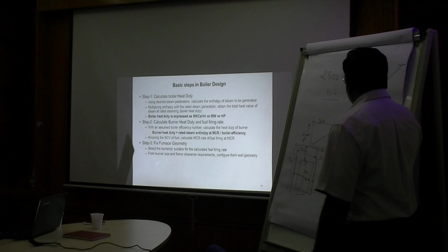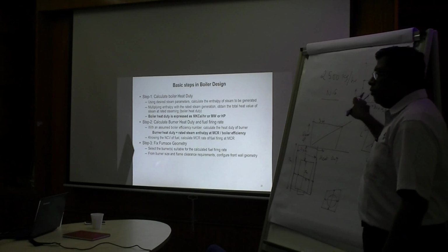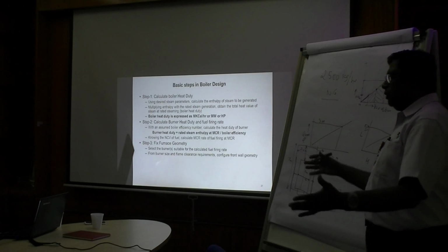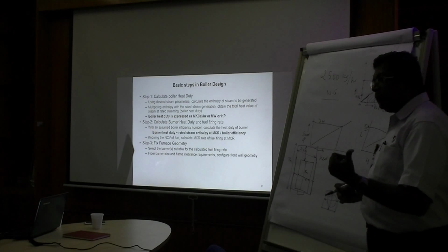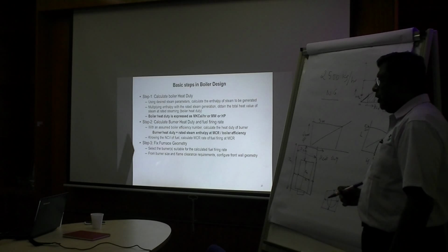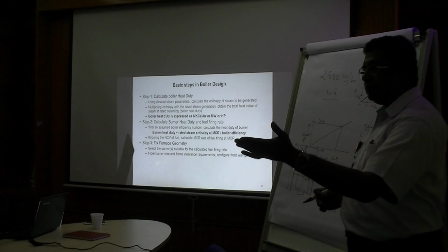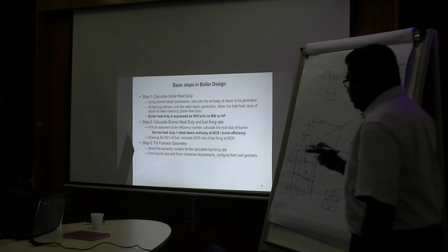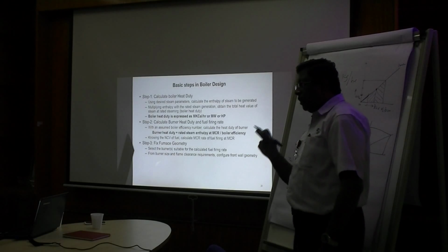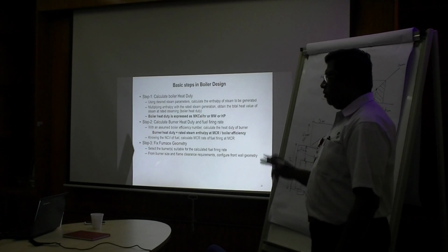So when you go for selecting or doing the engineering review, for example, you should ask the question: why are there only 2 burners? My boiler is supposed to be 150 tons. Why only 2? Why not 3 burners? Why not 4 burners? You go to PFK, 120 ton boiler, 3 burners. Go to CF Karte, auxiliary boiler, 100 tons only, 3 burners. You will see that as soon as the nameplate changes to beyond 60 tons capacity, 60 TPH, they have to have more than one. 120 TPH, they have to have more than two, and so on.